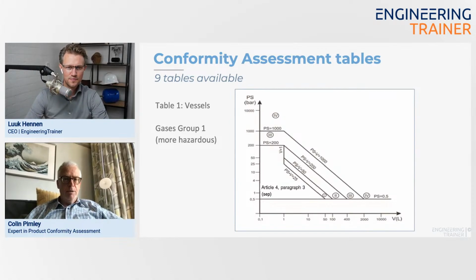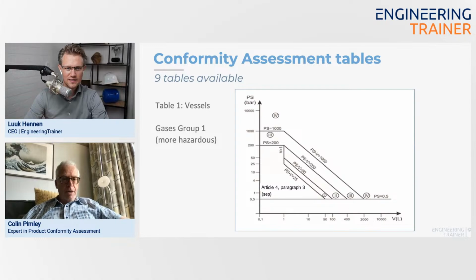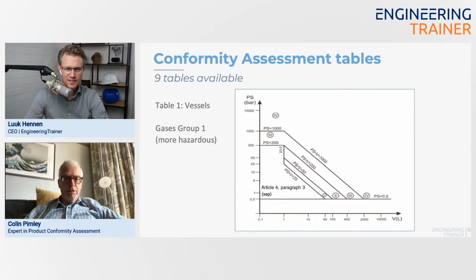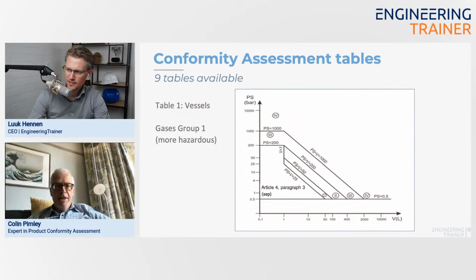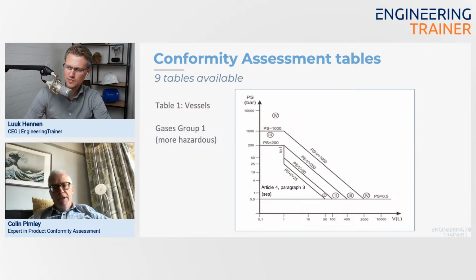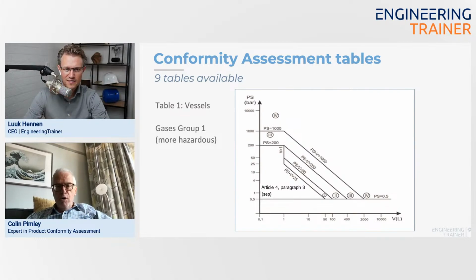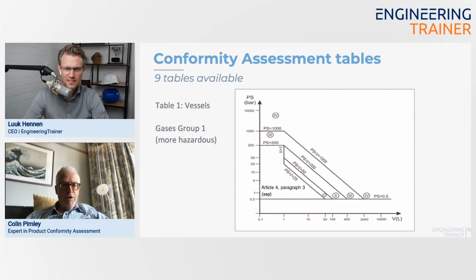It's on a log scale, but fundamentally, as you increase the product of the pressure and the volume, so your stored energy is increasing, and combined with the hazardous nature of the contained fluid, through these tables you are able to assign a risk rating to your equipment. We eventually pass a threshold, which I can't quite read myself now, where I think it's PS times V equal to 1,000. Yes, a thousand. So once your pressure times your volume is greater than 1,000 bar liters, then your pressure vessel is in the highest category that the PED foresees, which is category 4.